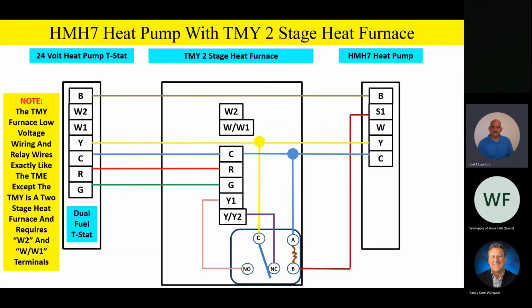All right, so basically, if we have a TMY two-stage furnace, it's going to wire exactly like the TME furnace. So this is why we haven't changed anything on that part of it. The only difference between a TME and a TMY furnace is the fact that the TMY furnace is a two-stage furnace, and it's going to have a W2 and a W/W1 terminal. But other than that, everything wires exactly the same as far as the B terminal, the S1 terminal, everything wires exactly the same. It's just that on the TMY, we're dealing with a two-stage furnace now.